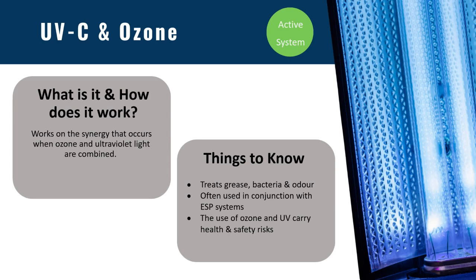UV lamps in direct contact with extract air provide a more intense effect than ozone injection. Things to know about the system: it treats grease, bacteria and odour. ESP combined with UVC and ozone units, the next technology we're going to consider, can be a highly effective pollution control solution.